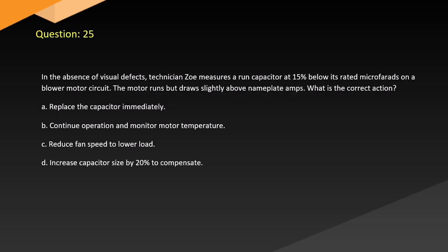Question 25. In the absence of visual defects, technician Zoe measures a run capacitor 15% below its rated microfarads on a blower motor circuit. The motor runs but draws slightly above nameplate amps. What is the correct action? A. Replace the capacitor immediately. B. Continue operation and monitor motor temperature. C. Reduce fan speed to lower load. D. Increase capacitor size by 20% to compensate.